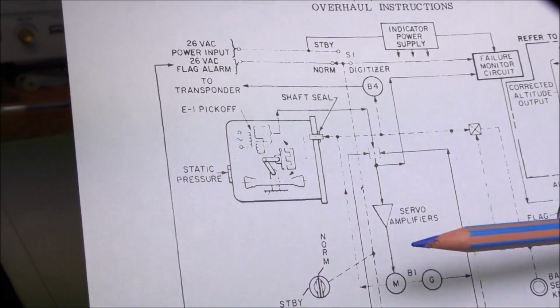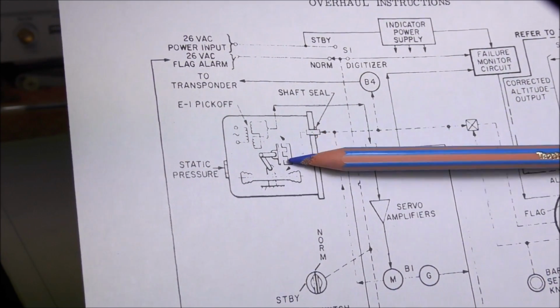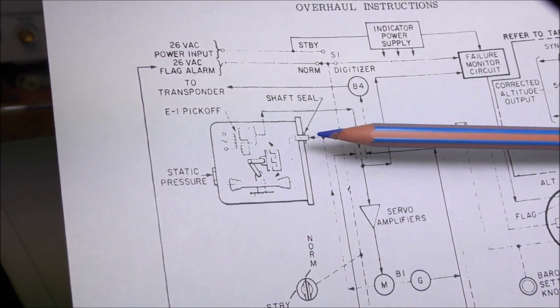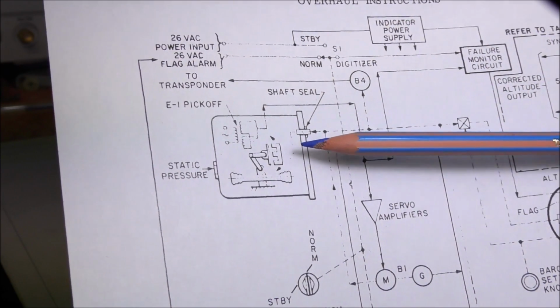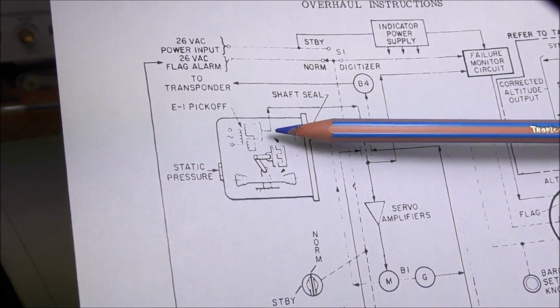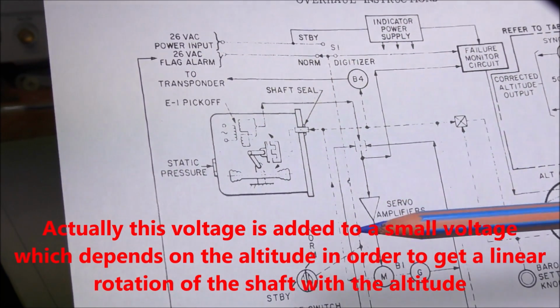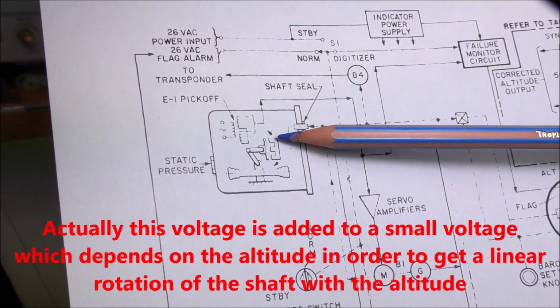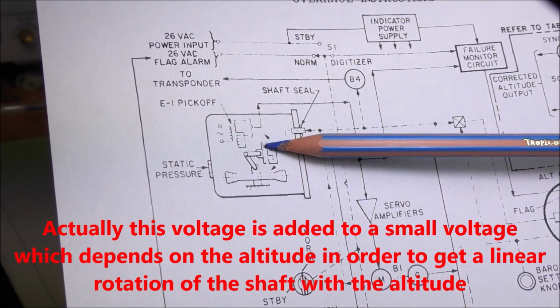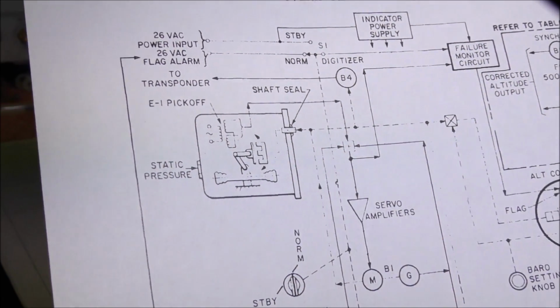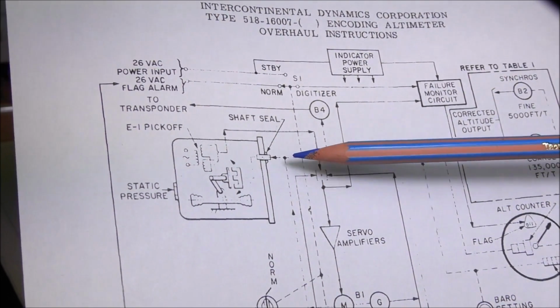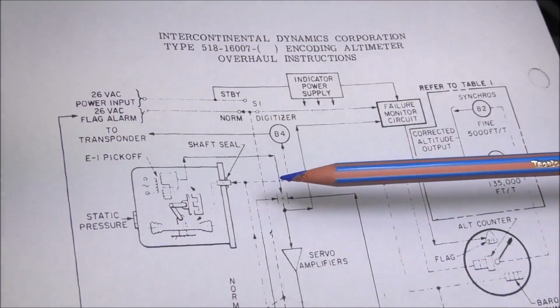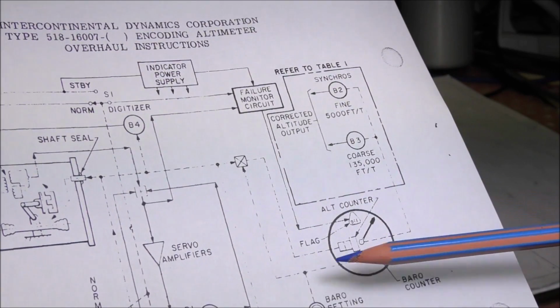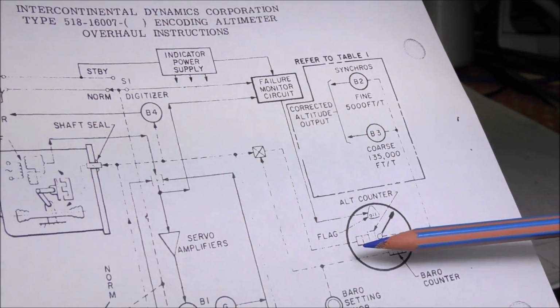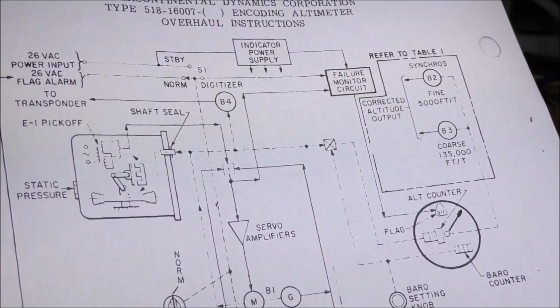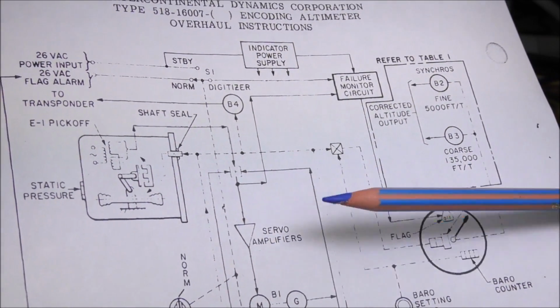So the goal of the system is to move the E bar here using a motor and reduction gears in order to have 0 volt as the output of the EI pick-off here, and in this case the E bar will be in front of the I bar, just in the middle, and the altitude corresponds to the rotation of this shaft. The shaft is linked to the needle here, so the needle indicates actually the movement of the capsule, and the movement is amplified using the servo control.